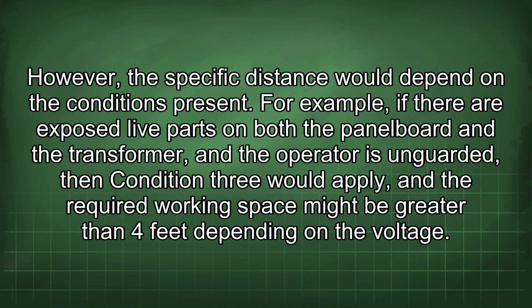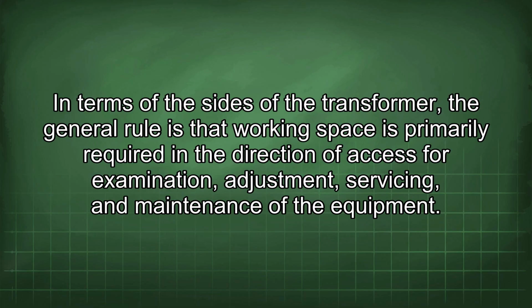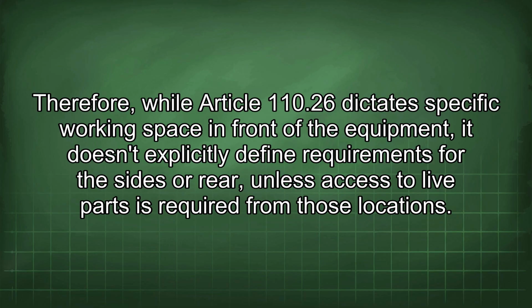For example, if there are exposed live parts on both the panel board and the transformer, and the operator is unguarded, then Condition 3 would apply, and the required working space might be greater than 4 feet depending on the voltage. In terms of the sides of the transformer, the general rule is that working space is primarily required in the direction of access for examination, adjustment, servicing, and maintenance of the equipment. Therefore, while Article 110.26 dictates specific working space in front of the equipment, it doesn't explicitly define requirements for the sides or rear, unless access to live parts is required from those locations.